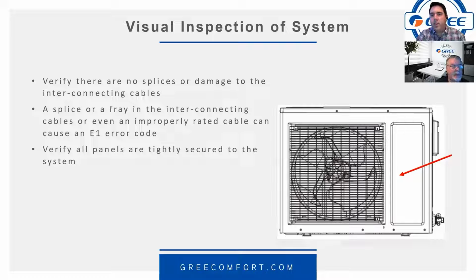The frayed wire is something that we questioned for a long time, and Richard did a lot of research and lab testing, and I've actually had several cases where I had a damaged wire and it was actually causing the E1 error code. You got to keep in mind, Keith, that the E1 error code is but a symptom. It could be a lot of different things, and not just to mention frayed or damaged control cable or interconnecting cable, also grounding as well. I've had several instances with our friends up in upstate New York where it's been a grounding issue that was sometimes causing E1, but also causing some random other error codes to pop up for what appeared to be no reason. Right. Yeah, the grounding can cause those random error codes and things. So it's always important to check that. Just make sure they're tight and secure.